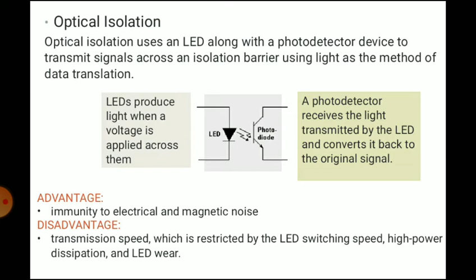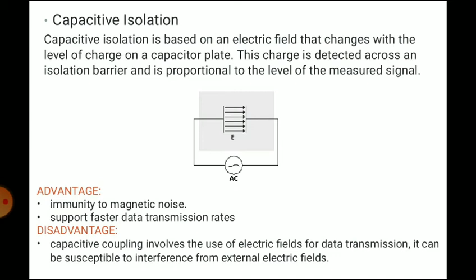Second is capacitive isolation. Capacitive isolation is based on an electric field that changes with the level of charge on a capacitor plate. This charge is detected across an isolation barrier and is proportional to the level of measured signal. So the advantage of capacitive isolation is immunity to magnetic noise and support for faster data transmission rates. And the disadvantage is that capacitive coupling involves the use of electric fields for data transmission. It can be susceptible to interference from external electric fields. So in capacitive isolation, the electric field is used for data transmission.